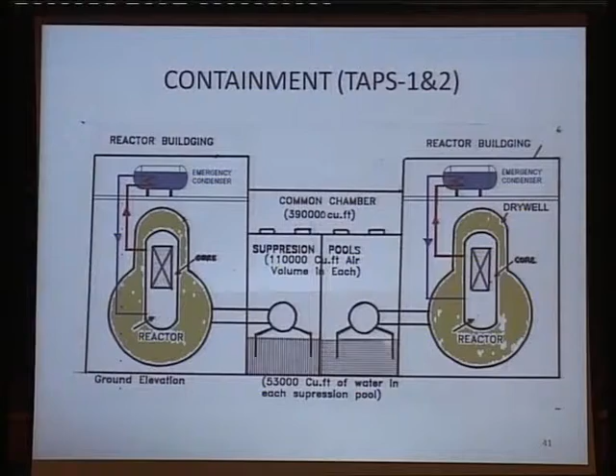In addition, from the original design itself, we have what is called an emergency condenser, located at great height so that it is possible to cool the reactor water through natural circulation. The principle is rather like a chimney: when air gets heated up, through its own buoyancy forces it rises because hot air is lighter than cold air, and cold air is then sucked in from wherever it's available. This is called thermosiphon. This arrangement is such that once we cool that condenser, the water doesn't require any pumping at all.